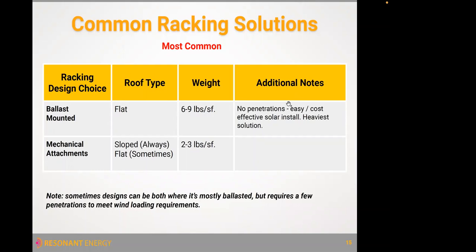And this is generally cost effective, but has a little bit more in the way of weight. So it's very important early on for a solar ready roof to make sure you have at least 10 pounds per square foot of additional dead load capacity to be able to plan for a ballast mounted array. In many cases, we have clients come to us with a flat roof where they say we only planned for 6 or 7 pounds per square foot of additional dead load.